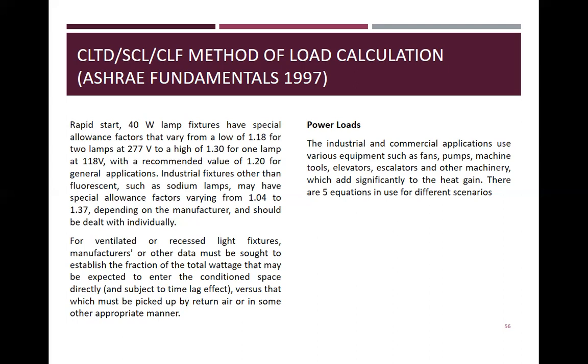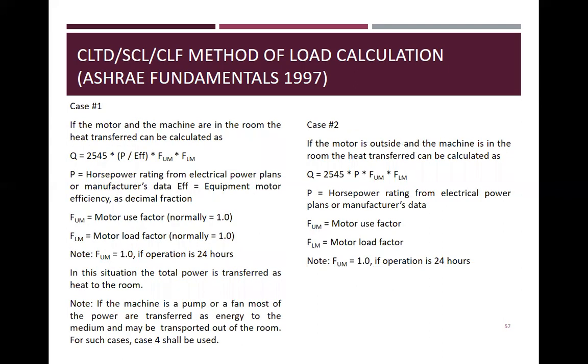There are five equations in use for different scenarios, machines, and motors. So case number one: if the motor and the machine are in the room, the heat transfer can be calculated as Q is equal to 2545 times P over the efficiency times FUM times FLM. P is the horsepower rating from electrical power plans or manufacturers' data. So 2545 is a conversion factor, BTU per horsepower hour. Eff is the equipment motor efficiency as a decimal fraction.